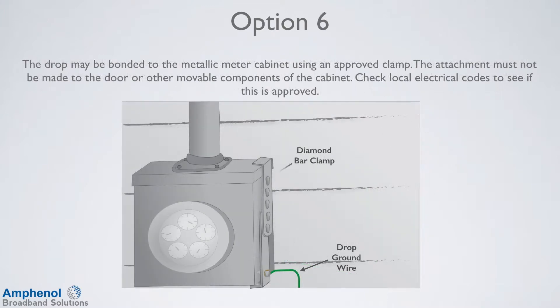With option number 6, the drop is bonded to the metallic meter cabinet using an approved clamp. The attachment must not be made to the door or other movable components of the cabinet. Before you use this option, make sure it is approved by the local power company and electrical inspector, as many power companies don't allow this. Clamps put on improperly block access to opening the meter box, and set screws can remove the enamel coating and allow rust to form.